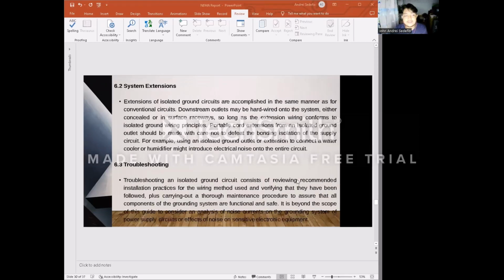System extension. Extension of isolated ground circuits is accomplished in the same manner as for conventional circuits. Downstream outlets may be hardwired into the system, either concealed or in a surface raceway, so long as the extension wiring conforms to isolated ground wiring principles. Portable cord extension from the isolated ground outlet should be made with care not to defeat the bonding isolation of the supply circuit. For example, using an isolated ground outlet for extension to a cooler or humidifier might introduce electrical noise into the entire circuit.